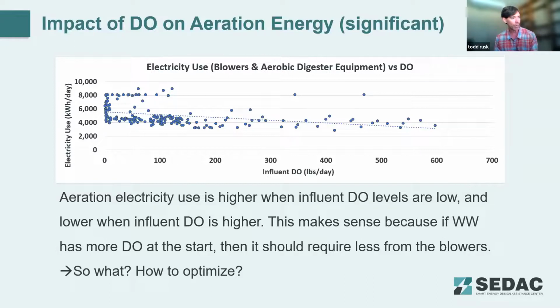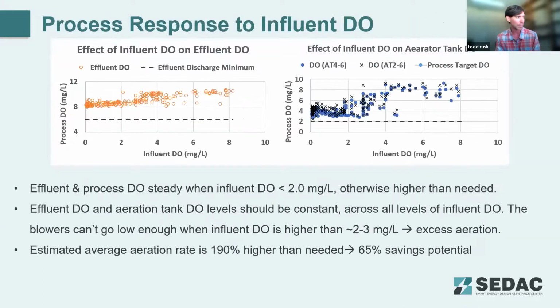But then when we go back to looking at energy, this shows it pretty clearly. As we have more and more oxygen coming in through the influent water in the plant, our blowers are doing less and less in energy consumption. And it makes sense—if for some reason the outside environment is pumping more oxygen into the water that's coming in, then the blowers and the aeration system have less work to do.